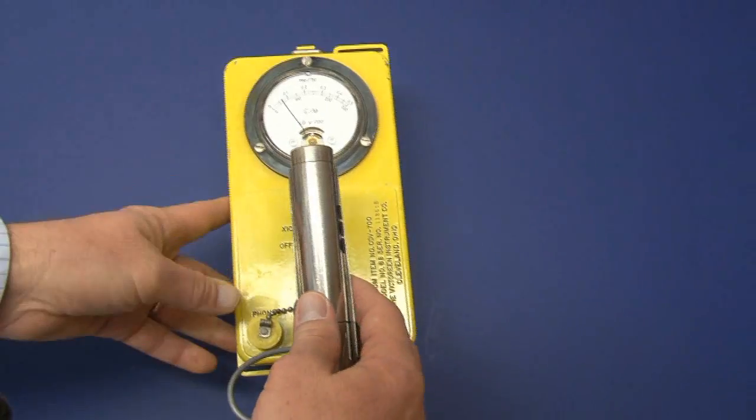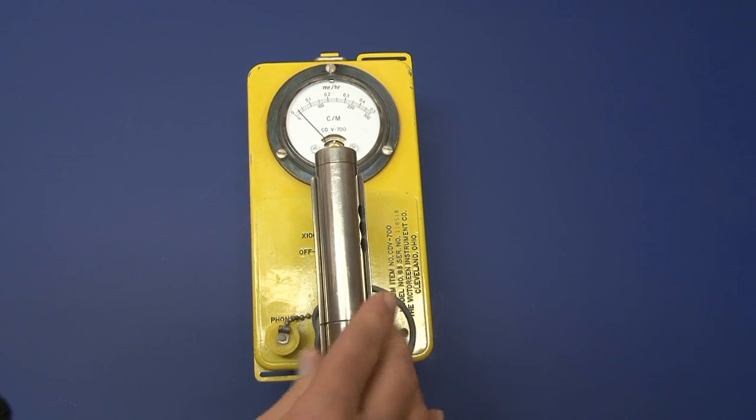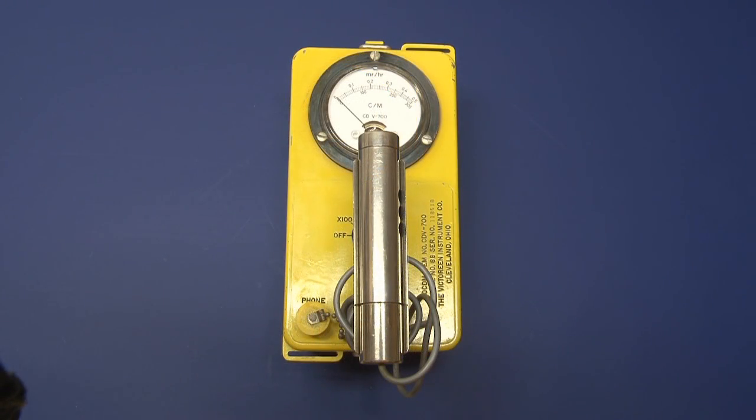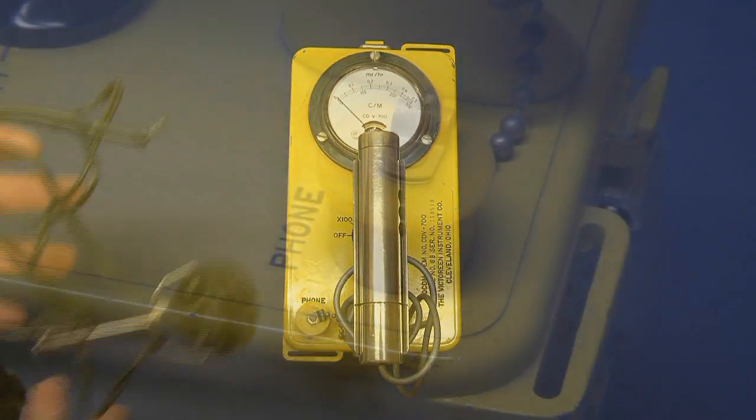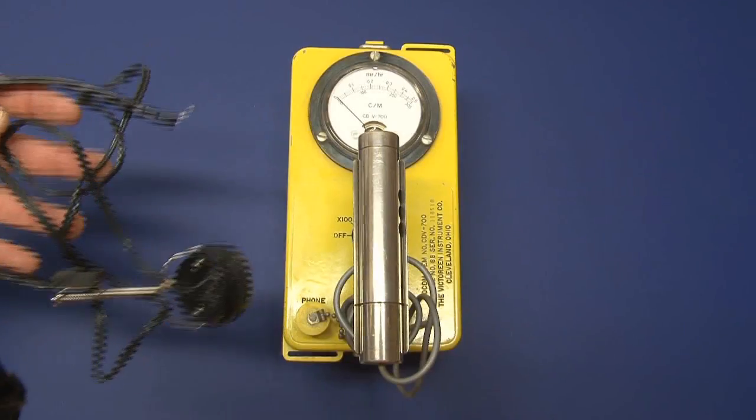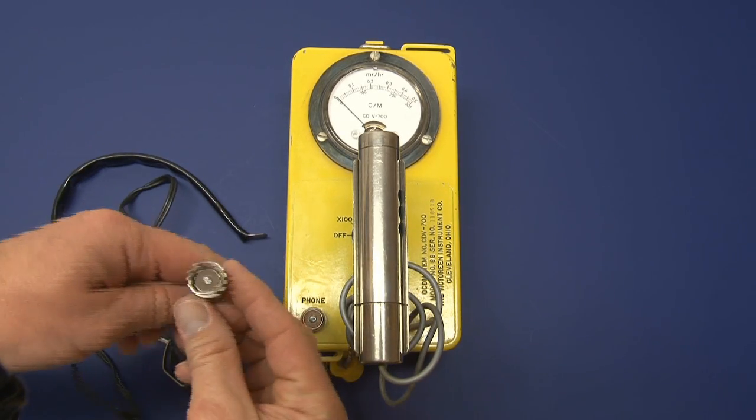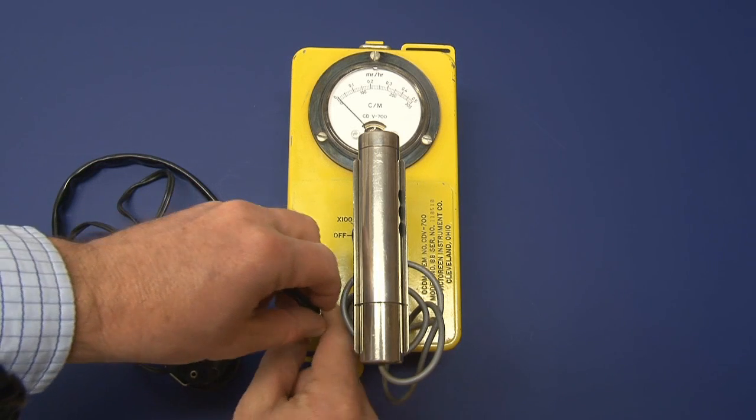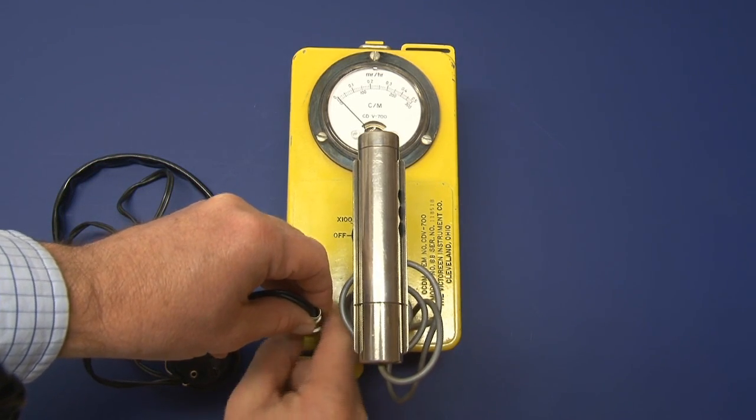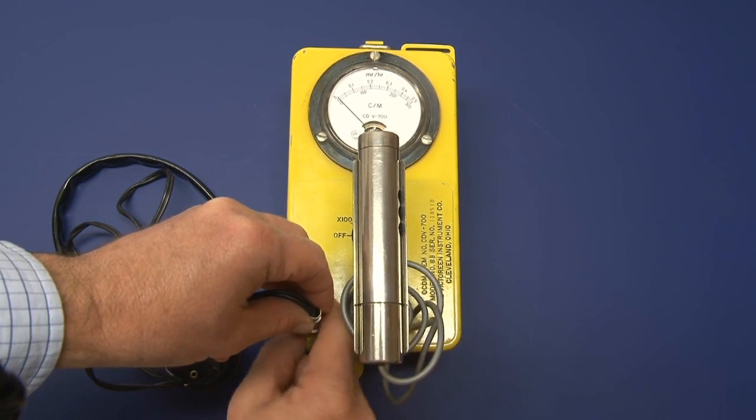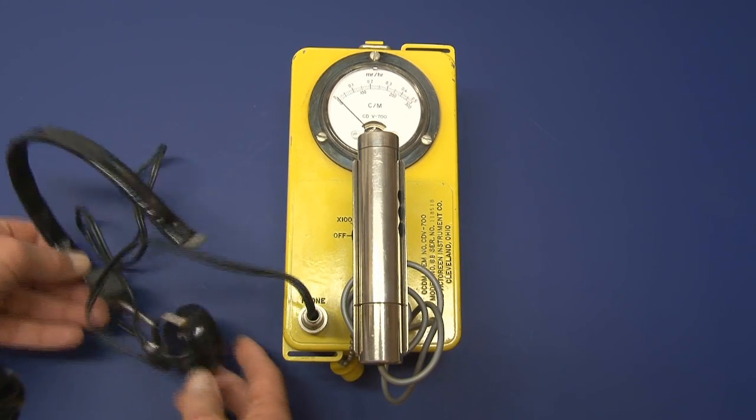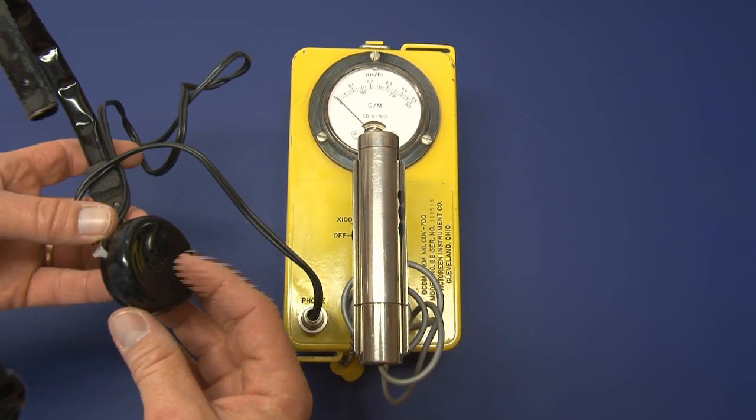This instrument does have an audio capability. It has a place here where you can plug in the earphones that were issued with the instrument. The instrument earphones look something like this. The idea is you can just remove this little cap here and you've got a little connector here that you can screw into place, and then you can hear the clicks through the speaker as the radiation is detected.